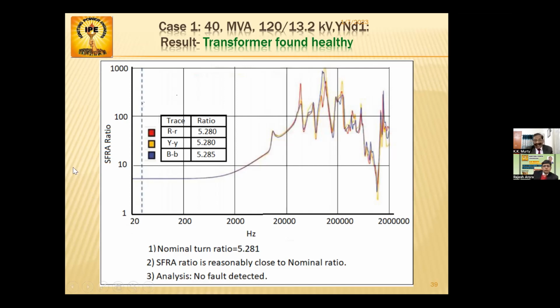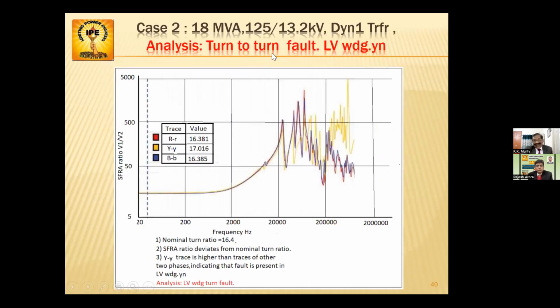Next, you can see the analysis of a turn to turn fault in LV winding. Here you can see a turn to turn fault in LV winding. When the LV winding has a fault, naturally the ratio will be more, because the HV winding is constant and the turns of the LV winding are the denominator. So if the LV winding has gone short, naturally the ratio will increase.